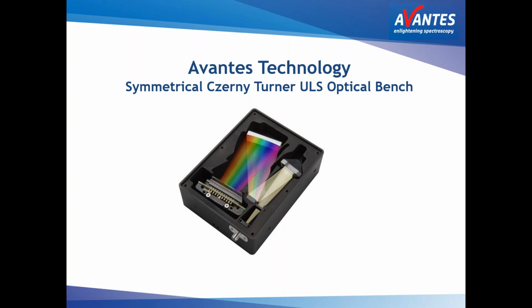To give you a little background on our technology, Avantes uses a Czerny-Turner optical design in our ULS optical bench, and the ULS stands for ultra-low stray light. To give you an idea of the physics of how this works, you have the optical entrance where the fiber optic fiber or probe would attach, and this can be either an SMA 905 or FCPC key connection.